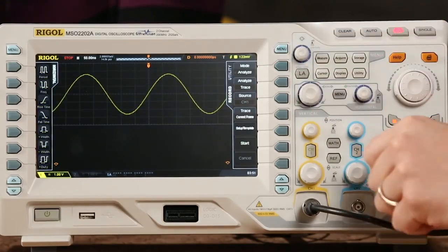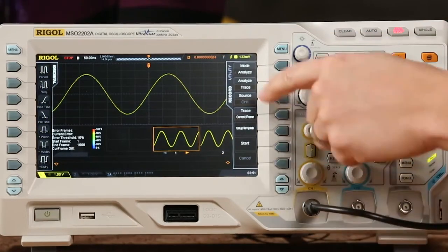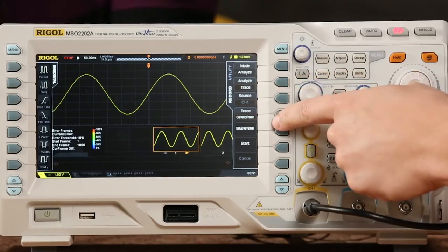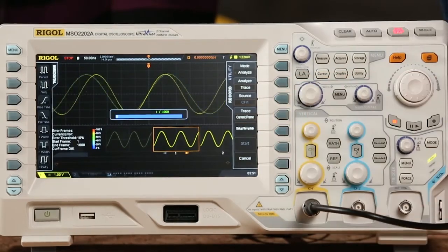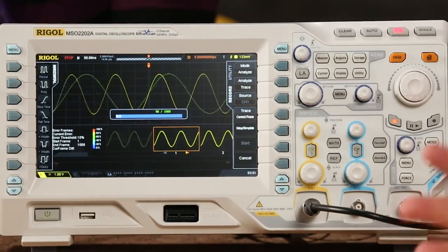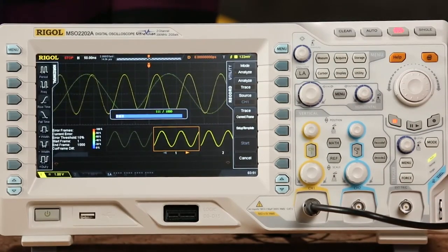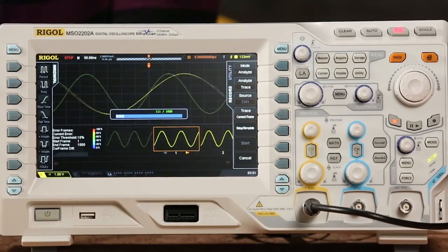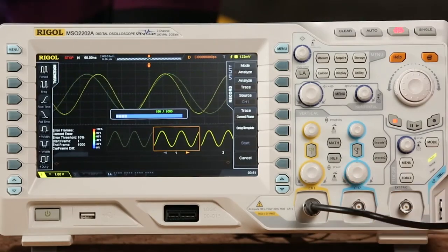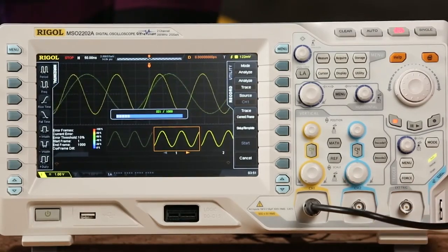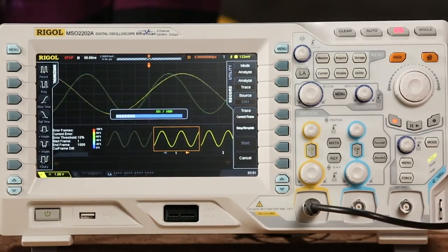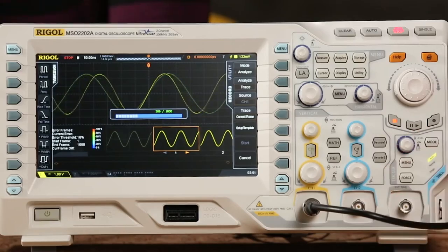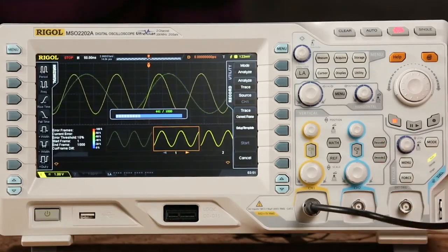So this is going to allow us to do some really neat front panel analysis on this scope. In trace mode, we can set this template, and from that first capture it took, it's going to look at how different each of the following frames are. Then we get a nice comparison. So it's actually doing RMS error data on a point-by-point basis across thousands of frames and thousands of data points per frame.